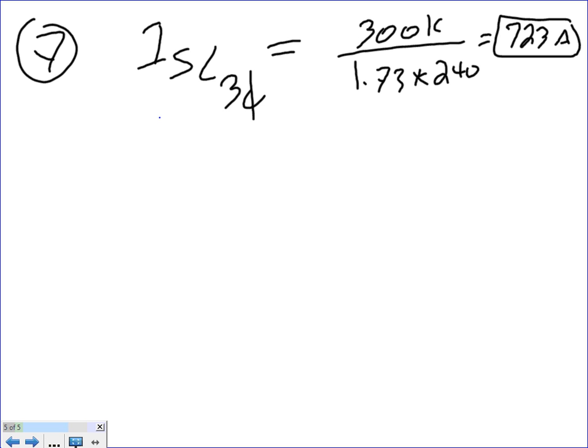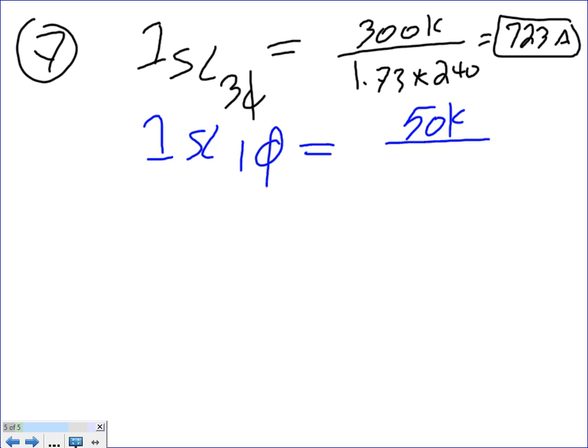Piece of cake. Then I secondary line single phase: how much single phase KVA do we have? 50 divided by 240, and if you do this, you're going to find 208 amps. So this is the line current on the secondary side, coming from the 3-phase and from the single phase, exactly like we did on the primary side.